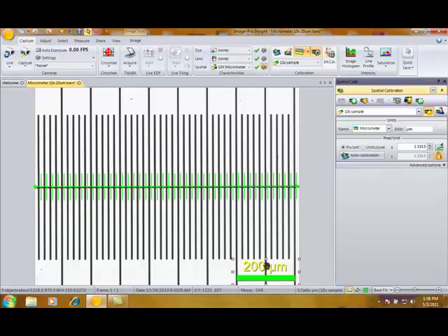I also have, as you can see here, a marker that I've set up previously to automatically display the units on the image. Within Image Pro Insight, you can also see what the current calibration is. In this case, my 10x sample calibration. So at this point, we're complete and ready to go on. One other important note, that if you do have a series of objectives, you can actually link these calibration files to a particular lens or objective, so that when you change your objective, the right spatial calibration will be applied to the image when you acquire it.